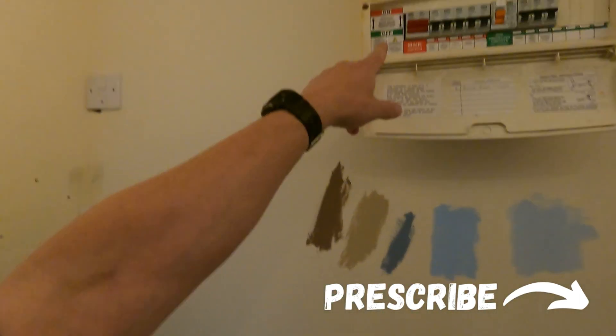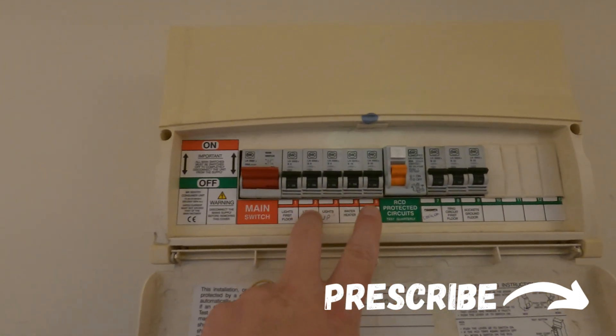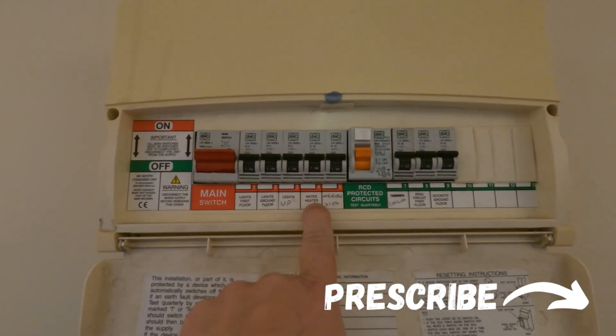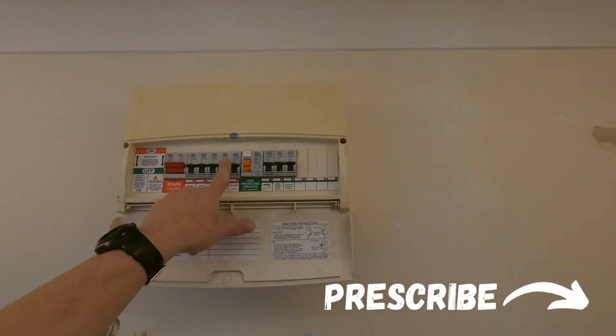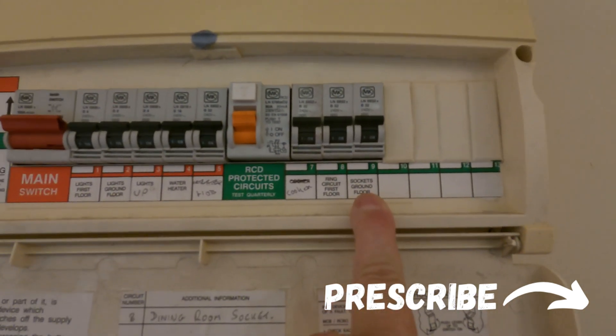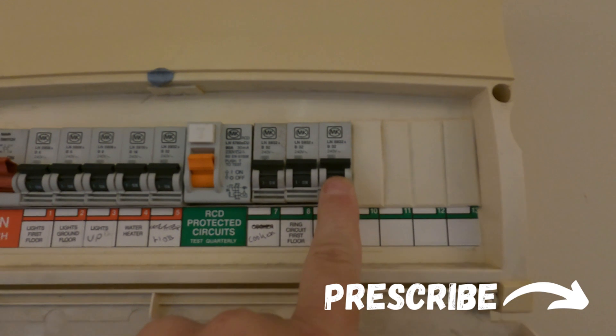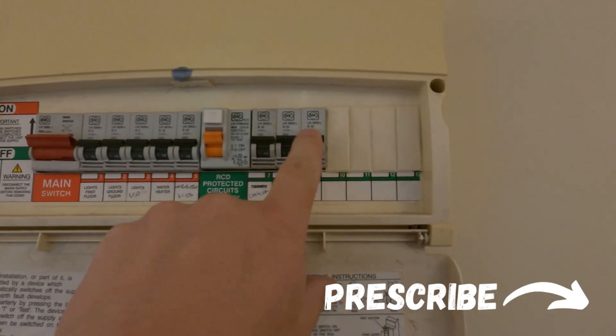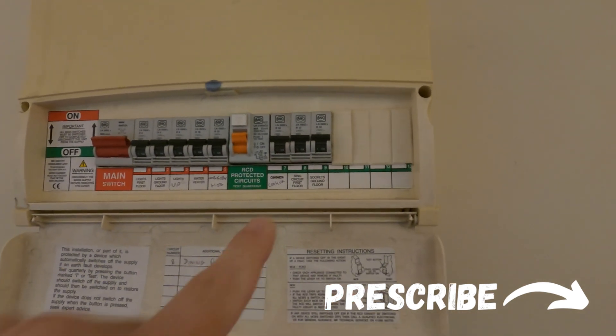What we are doing today is changing the consumer unit. We've got an old MK plastic consumer unit — half RCD and half non-RCD. We tested it yesterday; it's all OK apart from a water heater which showed a dead short, but the customer is not going to use it anyway so we'll just take that off. Also, the sockets on the ground floor are not a complete ring. What they've done is put three radials in there, still on 32A, but the cable is only 2.5mm so it's not rated for 32 amps — we need to possibly separate some of these and put them on 20 amps.